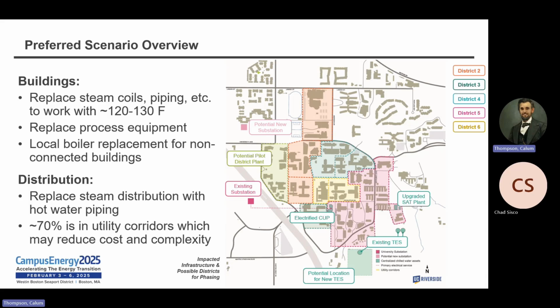So for those buildings with existing steam, that means replacing the piping, the coils where appropriate, and the process equipment where appropriate, such as the sterilizers. Where buildings have existing hot water, we look at the air handler units, etc., to expand the coil capacity to meet essentially a 130 degree supply temperature.